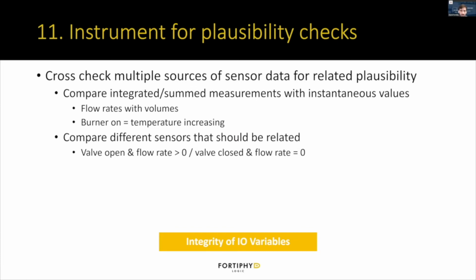Practice number 11 is instrumenting for plausibility checks. The idea behind this is to cross-check multiple sources of sensor data for related plausibility. Some examples could be comparing the integrated or summed measurements with the instantaneous values. Imagine you have sensors for flow rate in a pipe, and also a sensor for the tank level or the volume of the tank it's flowing into. You can integrate the total amount that has flowed through the flow sensor, compare that with the level of the tank, and calculate what the volume of the tank is. Is there a major discrepancy between the two sensors?